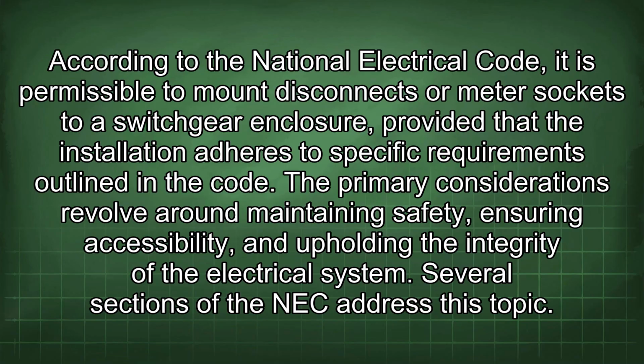According to the National Electrical Code, it is permissible to mount disconnects or meter sockets to a switchgear enclosure, provided that the installation adheres to specific requirements outlined in the code. The primary considerations revolve around maintaining safety, ensuring accessibility, and upholding the integrity of the electrical system. Several sections of the NEC address this topic.